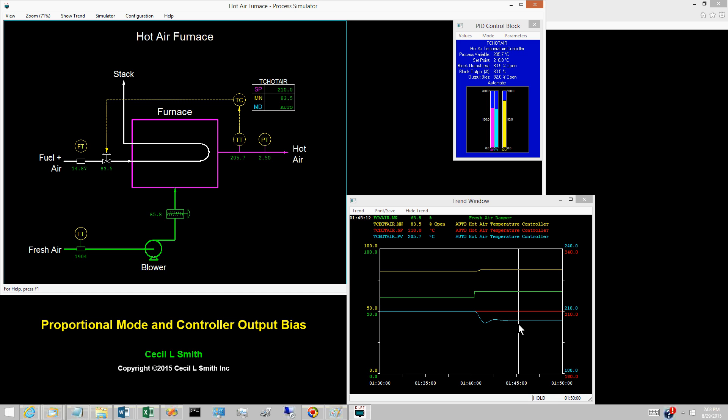Controls first appeared in the process industries in the form of proportional only pneumatic controllers. How did the process operators cope with droop? The early controllers provide a knob labeled Manual Reset that adjusted the controller output bias M sub R.